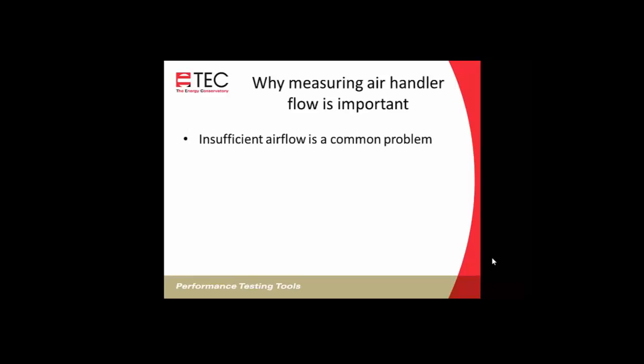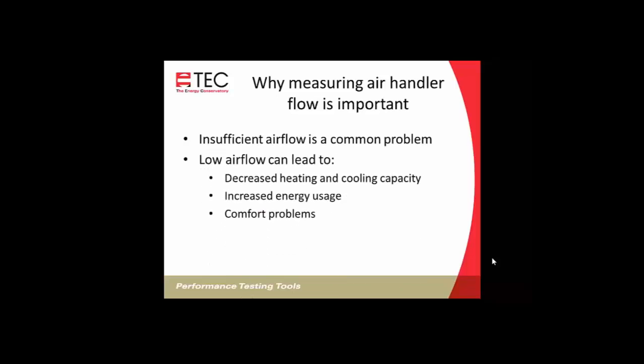So why is measuring airflow important? Insufficient airflow is certainly a common problem that we see. And low airflow can lead to decreased capacity, certainly decreased capacity if you're not getting the proper airflow. You could even be freezing up a coil if not enough air is moving across it. You'll see increased energy usage and certainly comfort problems if the air conditioning or heat isn't being distributed to where it's supposed to be properly.